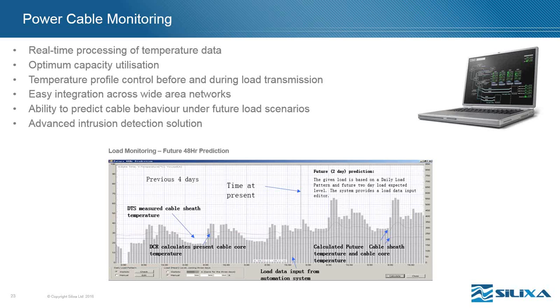Using real-time thermal rating software, it is possible to predict in real-time thermal bottlenecks and overload conditions. The Silixa solution provides fundamental monitoring in the case of circuit maintenance and reinstatement regimes. Under such conditions, the network transport link can be more heavily loaded than it would be under normal conditions. Again, this is a distributed temperature monitoring application.